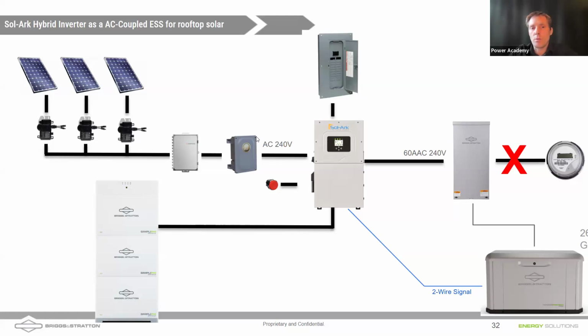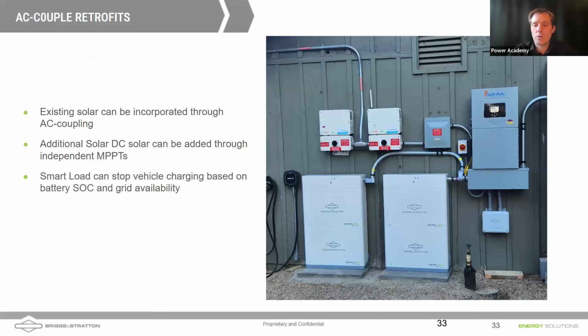What's this, Daniel, and why might I want something like this? Well, that's a lockout module from our SimpliPHI choice line of transfer switches. What that will do is turn off the AC coupled solar or open up a circuit so that the AC solar cannot run while the generator is running. One thing I also want to mention, Nathan, is you notice in your diagram here that you don't have a disconnect. That's because inside of our transfer switches, those are service rated disconnects. So as long as it's inside of the meter, you can use that and don't need a separate disconnect. That's a great point, Daniel.